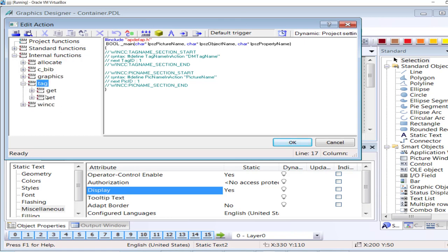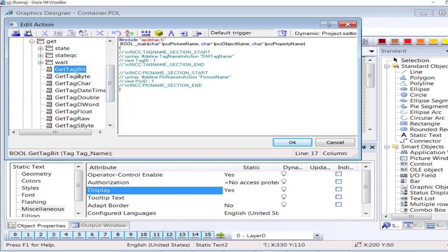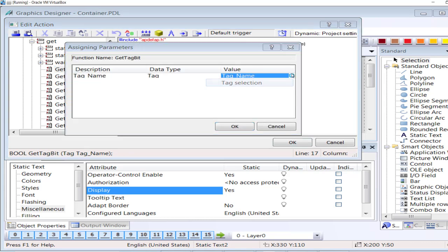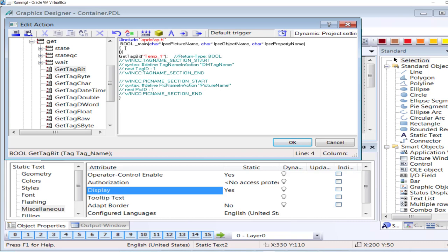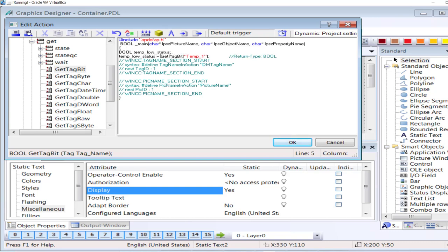Similarly, I will associate a script with the second text as well. GetTagBit again — you have lots of functions here but I am just interested in GetTagBit. The tag is Temp1 at I0.0. Click OK. Now same as before I will create a new boolean variable 'TempLowStatus'. I will assign the status of the signal returned from this GetTagBit function, but here I am going to do something slightly different.